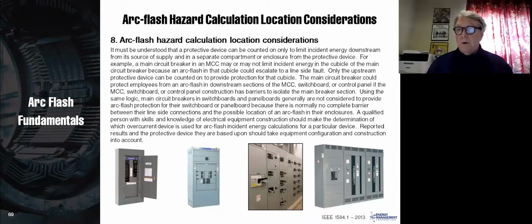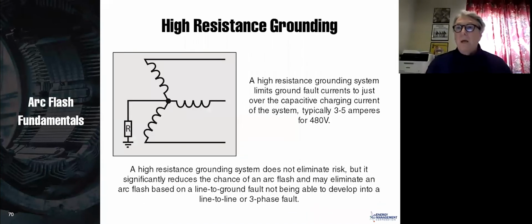So if you have a situation like this, you can have two labels, one for this incoming gear and then one for the other sections. Or if you want, you could just take the higher calorie level on the incoming gear and label your whole panel that. There is nothing to prevent you from doing that if you would like to do it.